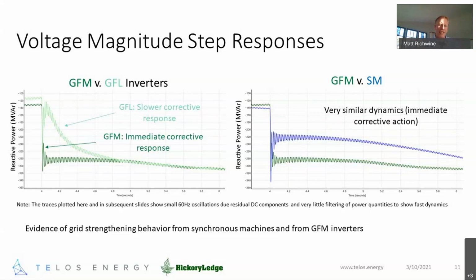But what we really wanted to zoom in on is the dynamics, and particularly in the short time frame after the event. You can see that for the grid forming inverter, the reactive power response goes down very quickly, basically immediately, and then stabilizes. In contrast, the grid following inverter has maybe a little bit of a wiggle at the very beginning, but then it has this gradual dynamic decay down to the new value. I understand the scale is hard to read. This is about 2 seconds of simulation time, or about 200 milliseconds per division. So we can see a pretty substantial difference in about the first half a second after this event.